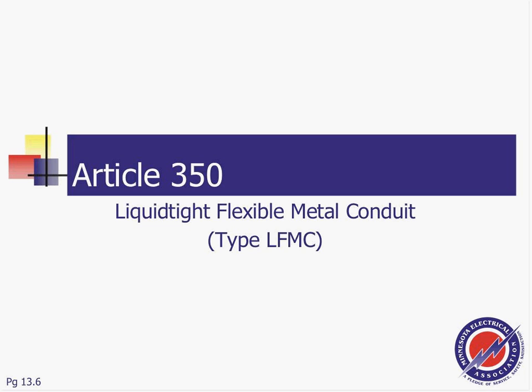So the next application, guys, is Liquidtight flexible metallic conduit. If you are in a dry location or damp location, not a wet location, then you can use flexible metallic conduit. If in a wet location and you need flexibility, then you have no choice but one of the options. If you tie to equipment in a wet location, and you need flexibility and vibration, your choice because of the wet location will be Liquidtight flexible metallic conduit.